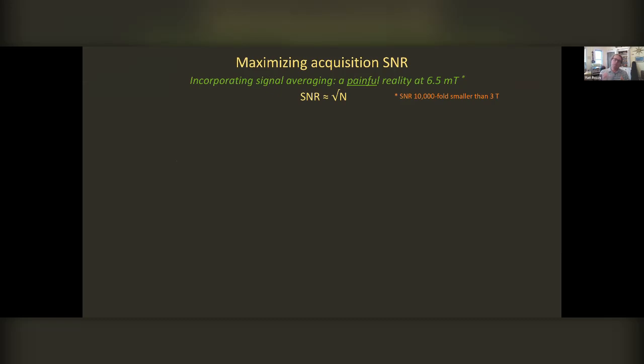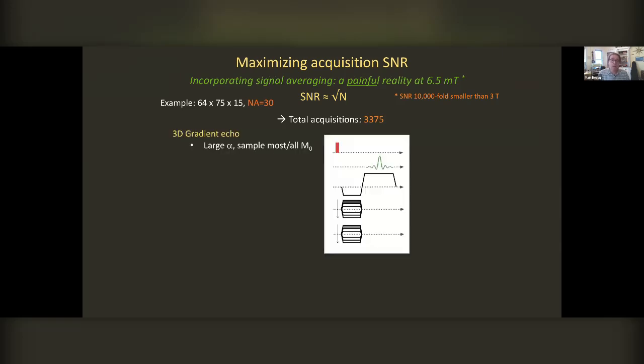And so signal averaging is a painful reality at 6.5 millitesla. You win by the square root of the number of averages, which isn't great, but at least you're winning. So in my lab, if we want to typically acquire a 64 by 75 by 15 matrix, we need about 30 averages.